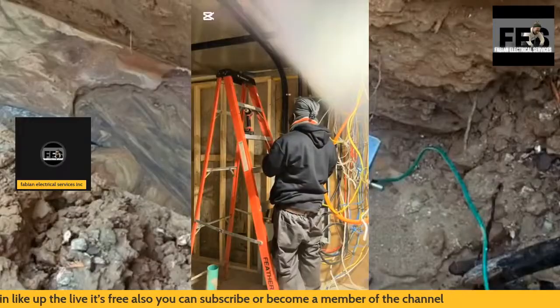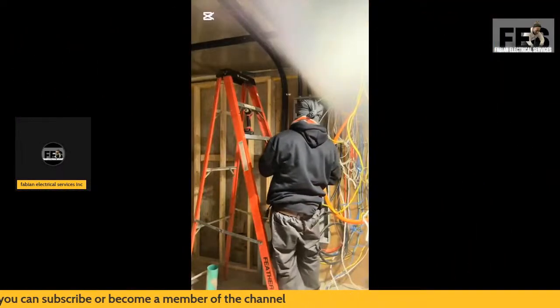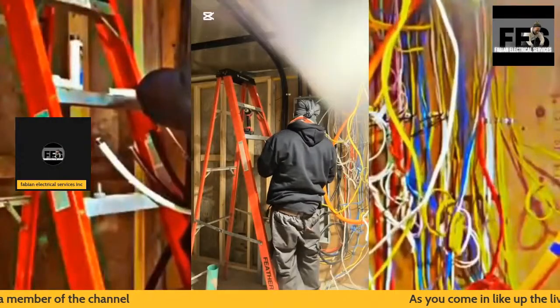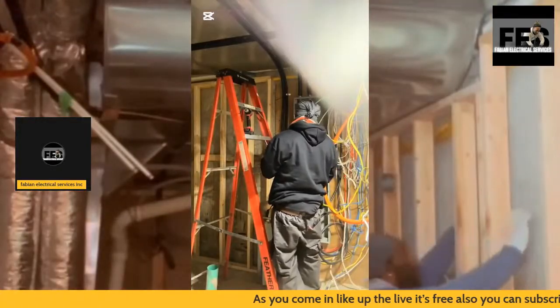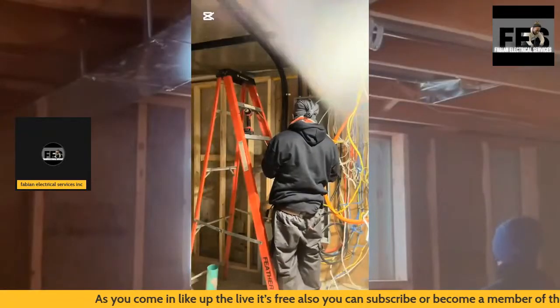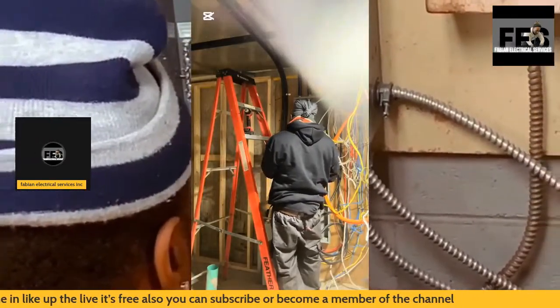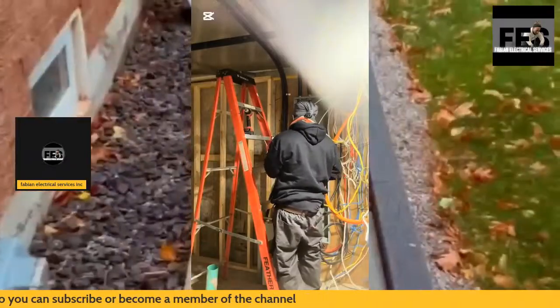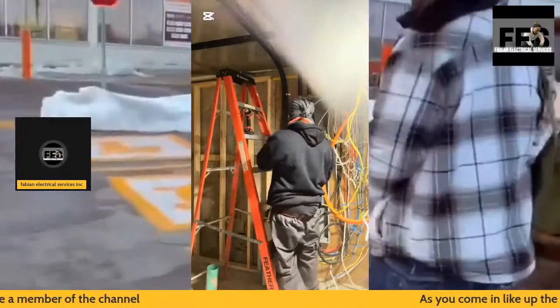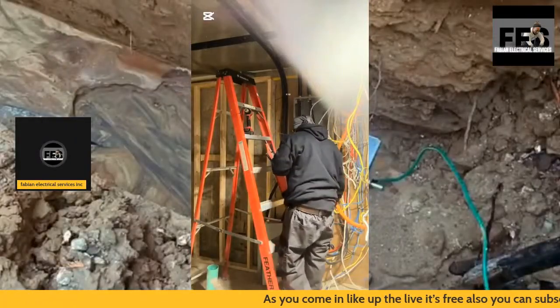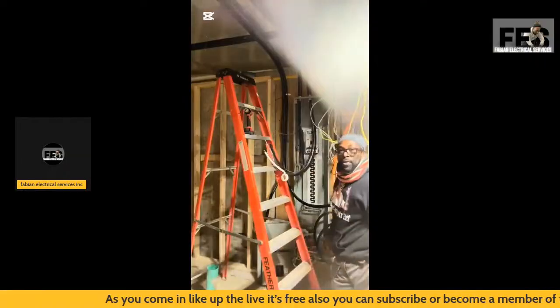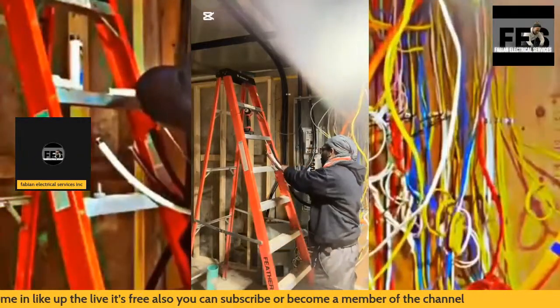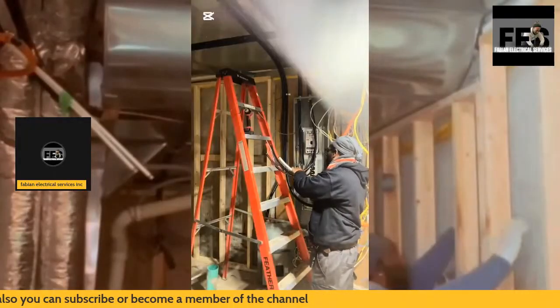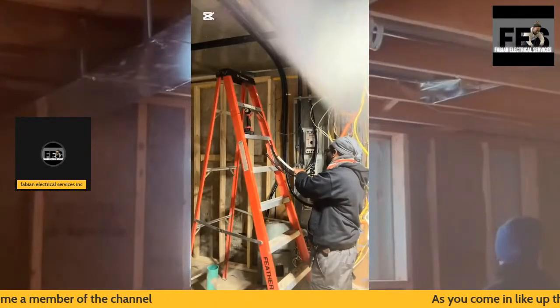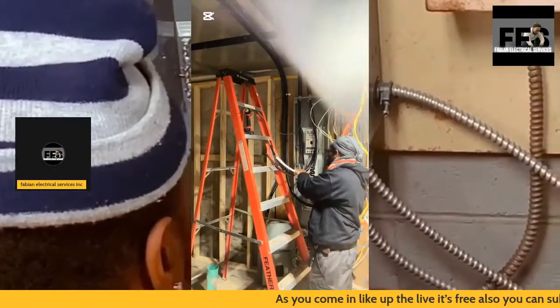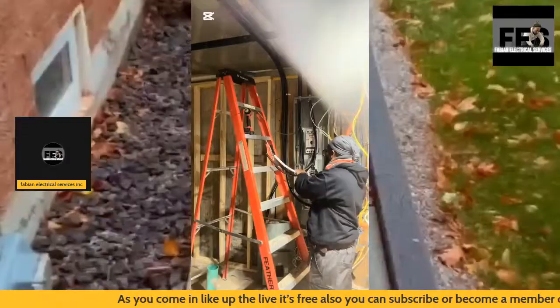Again, it's within my code compliance, and what I'm doing right here is simply phasing my wire - it's called electrical phasing of the neutrals. It's a code rule, and we always have to stay within our code compliance. The code rule states that when installing your neutral, it shall be an identified conductor. Right now it's not, so I have to make it one by using white electrical tape to phase it.